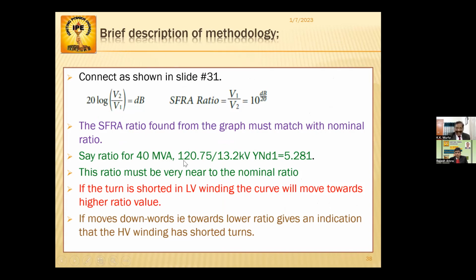The ratio of 40 MVA, 120.75 divided by 13.2 kV, Y and D1 is the ratio. Nominal ratio means this is the Y and delta 1. YN means star, and this is D. So the winding of star is phase to neutral, which has to be taken care of, which is inductively connected with the delta winding. Of course, rather, magnetically connected with the delta winding.